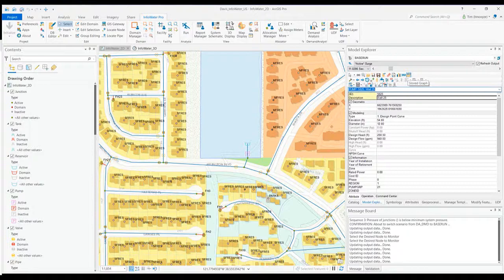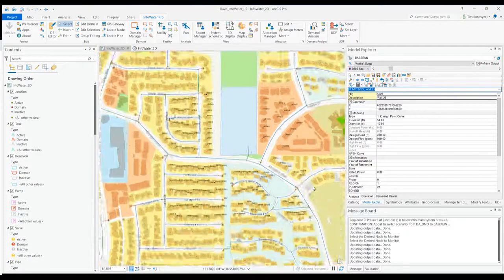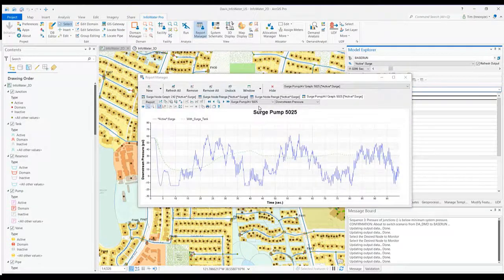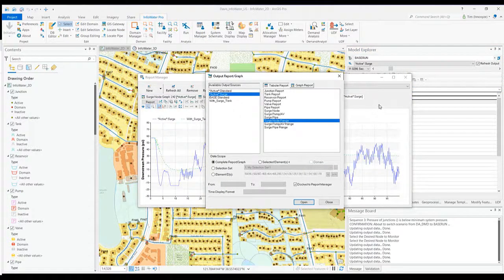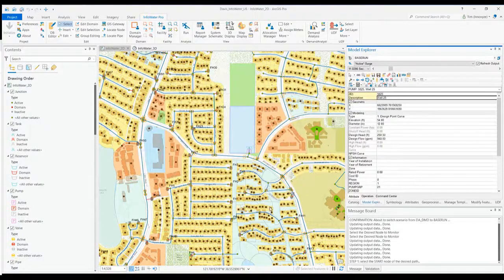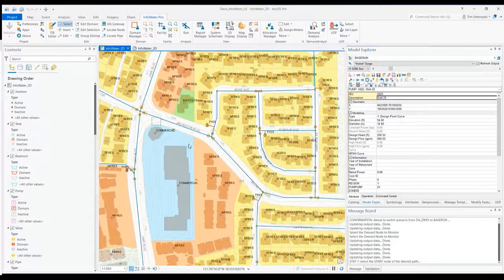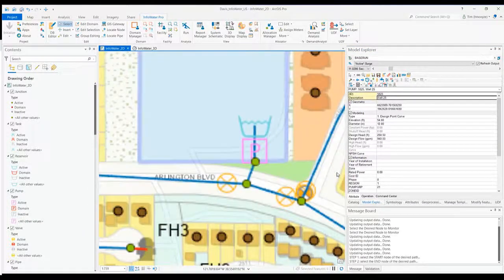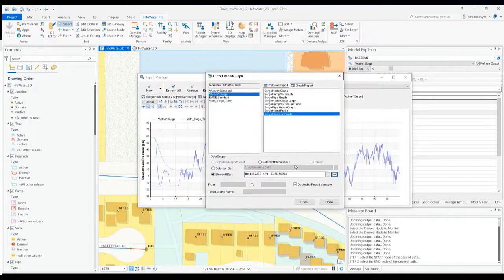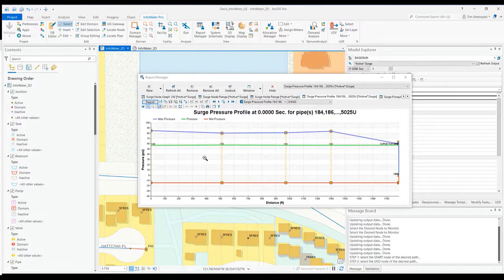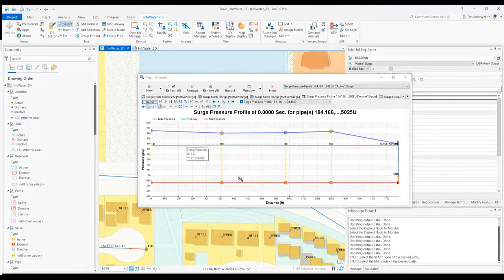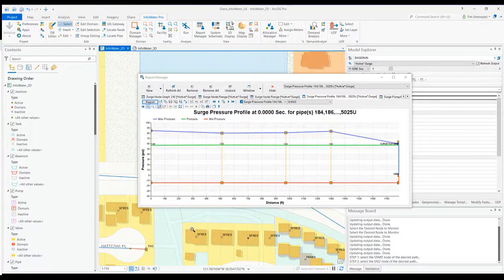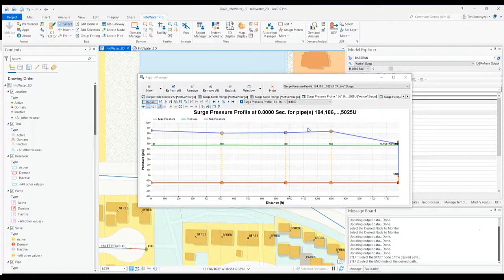Other analyses that are particularly useful with InfoSurge: if I go to my report manager and create a new report, I want to look at a number of different pipes and see how that transient affects them. Let's look at the range of pipes from here to there. We can see the max pressure, the average pressure, and the minimum pressure occurring during this surge event. I've got huge pressure fluctuations here, over 80. Some of my negative values here are definitely being affected by that transient event, quite a large water hammer.